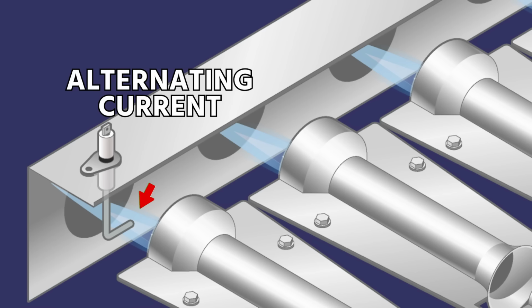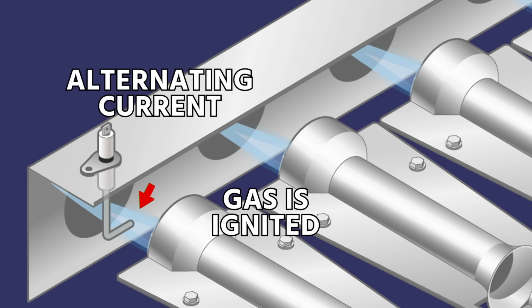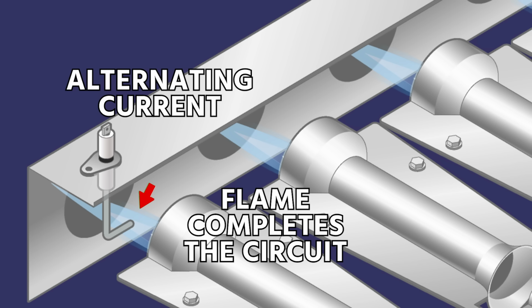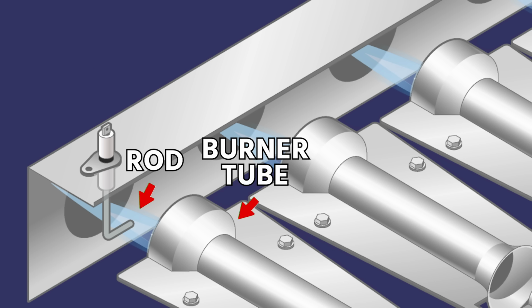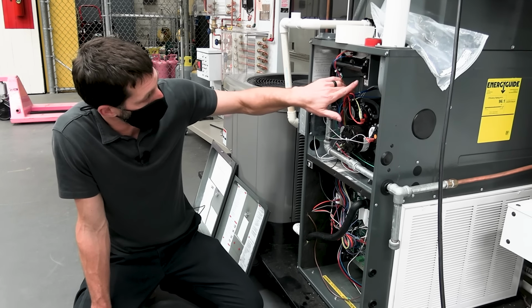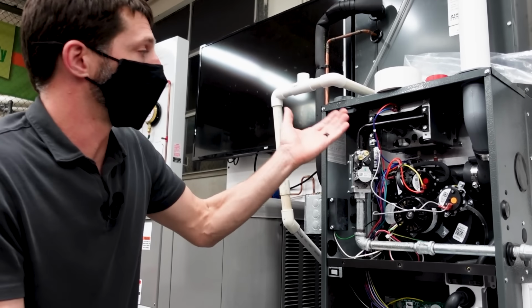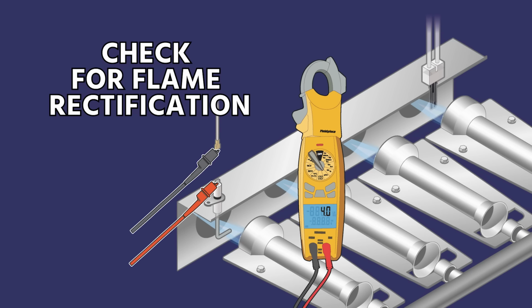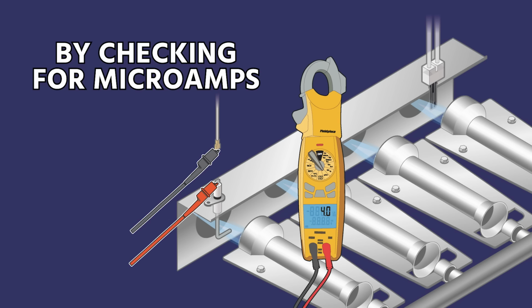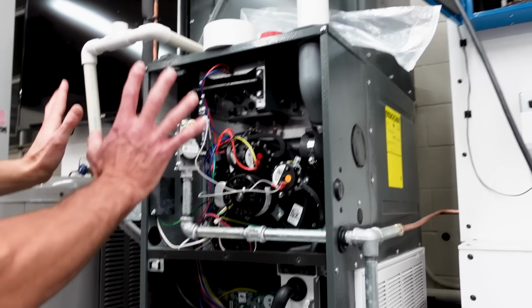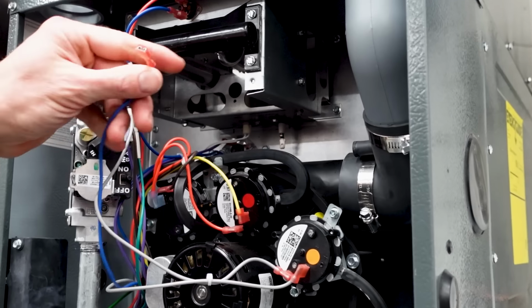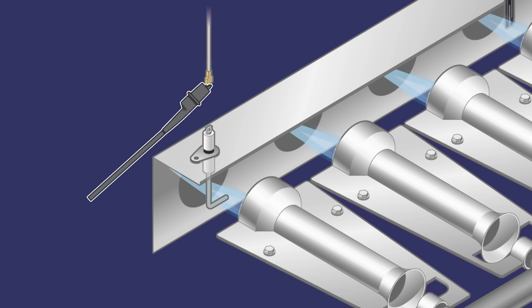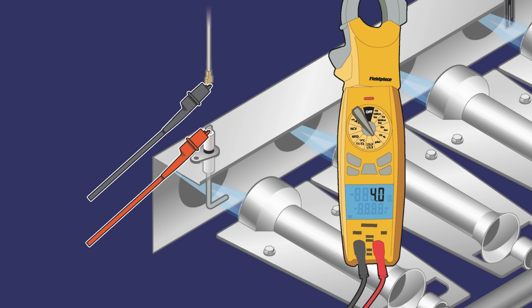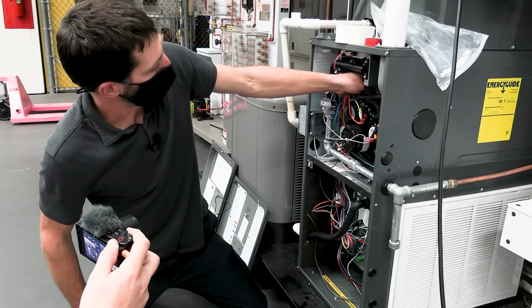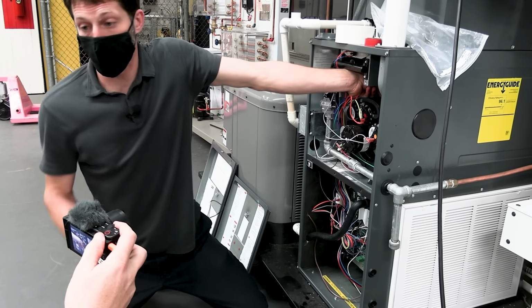And what's happening is when the gas is ignited, the flame completes the circuit from the rod to the burner tube flame retention head. That rectifies the alternating current, and it becomes direct current. You can check for flame rectification by checking for microamps with your multimeter. The power is off, and you would just disconnect right here and put one probe in here and one probe here. It's microamps, so it's very little. It goes through the meter and it's displayed on the meter. A lot of times it's 3 microamps, and that's once again direct current. And that is in series. You're wiring it in series, correct, yeah.